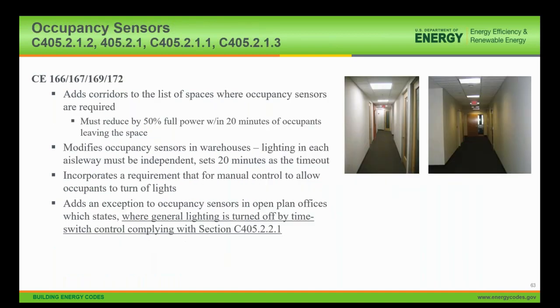And beyond parking garages, occupancy sensors also had some modifications. One is that there was a list of spaces where occupancy sensors were required. Corridors were added to that, as shown in the image on the right. You must reduce power by a full 50% within 20 minutes of the occupants leaving the corridor. It also modifies how occupancy sensors in warehouse spaces were configured, with lighting in each aisleway. If you think about rows and rows of shelving and then lighting between them, the lighting in between them creates your aisleway.